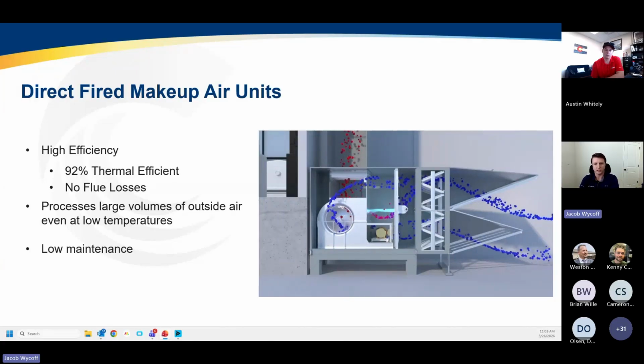So number one, they're extremely efficient. With 100% outside air direct fired units, you have that combustion process occurring directly in the airstream, which allows you to get the maximum possible efficiency out of the fuel that you're providing. That gives you your 100% combustion efficiency or your 92% sensible thermal efficiency. Because we have no heat exchanger, we therefore have no flue losses. You're not losing any of that heat up through the roof of the unit or up through the roof of the building as you're exhausting those flue gases because there is no flue on the unit.